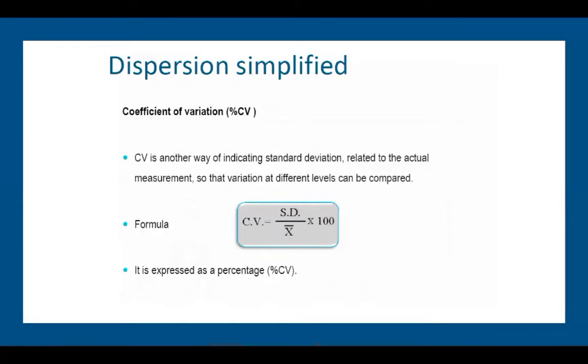For this, you must have seen accreditation bodies also ask for CV % rather than SD, because with CV they can see variation in different analytes. And when you are submitting your CV, submit only up to 1 decimal point, because only that much variation they want to see. Your calculator will give you CV 6.38296 or 5.4332. That much is not required.